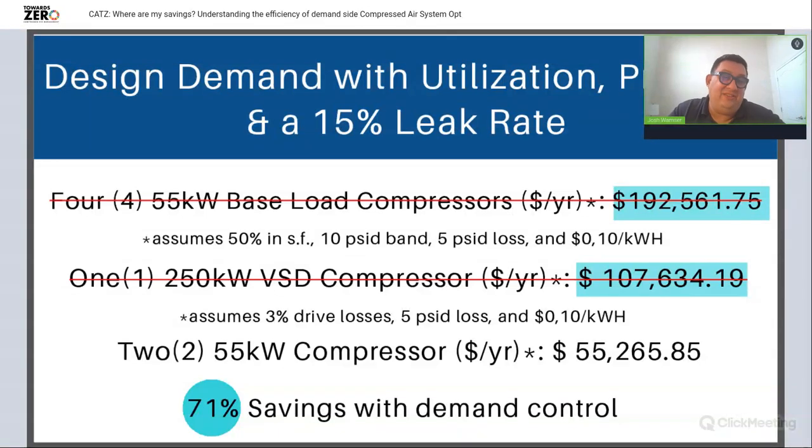In fact, the last I know, they purchased 2 additional compressors, and now they're running all 6 compressors with no demand change from when I had it set at 2 compressors. So even when we think we win, sometimes we don't win.